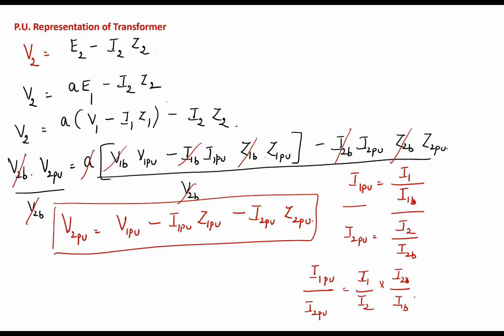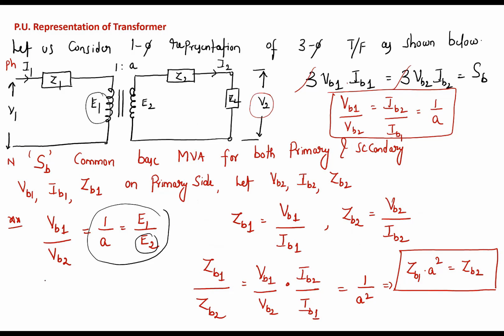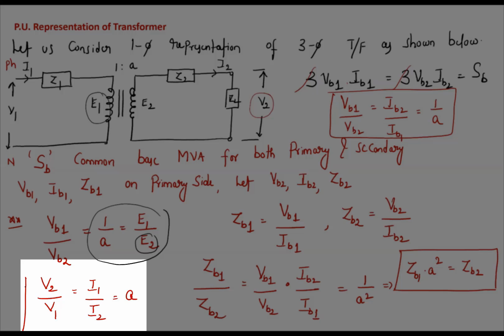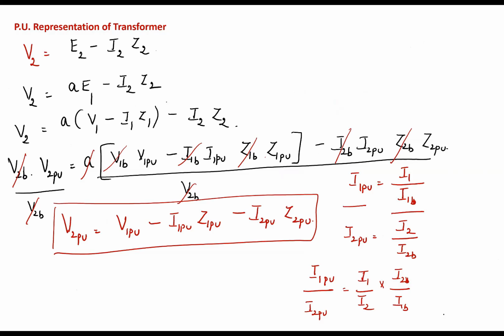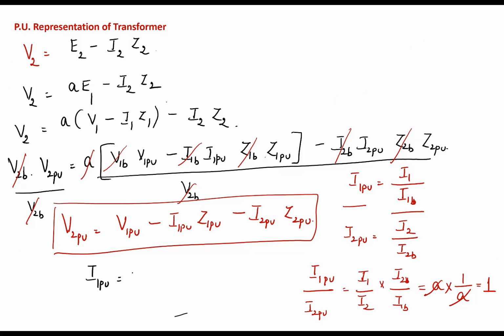Now, if you consider an ideal transformer, where V2 by V1 is equal to I1 by I2, how can you write A? In an ideal transformer, V2 by V1 is equal to I1 by I2, which is equal to A. So if you apply the same concept here, I1 by I2 will become A, and I2 base by I1 base will become 1 by A. So this value is equal to 1, which implies in a transformer, I1 per unit is equal to I2 per unit. Let us call the common value I per unit. So the per unit current of the transformer is the same on both primary side and secondary side. That is the third important relationship. So per unit value of current on HT side and LT side is the same in case of an ideal transformer.